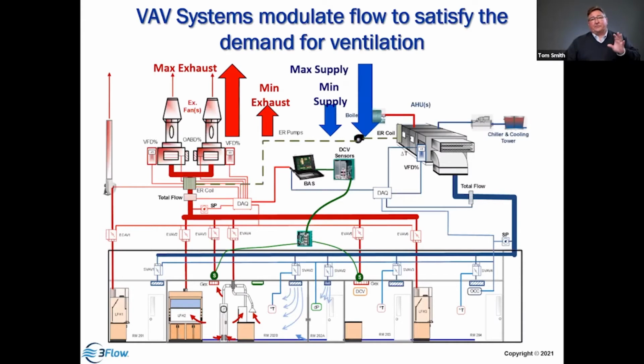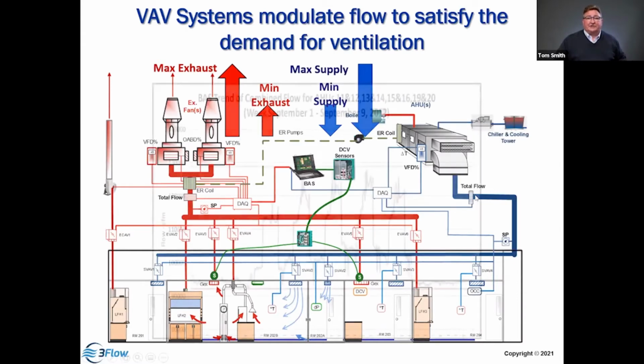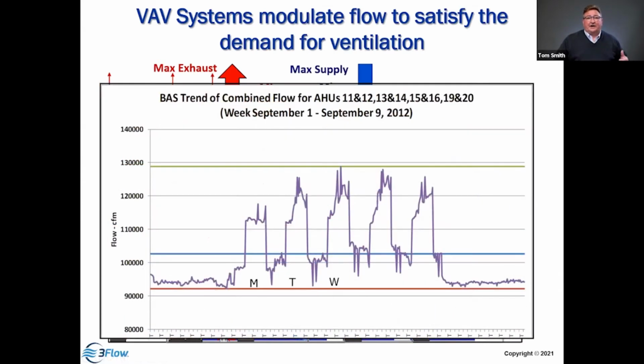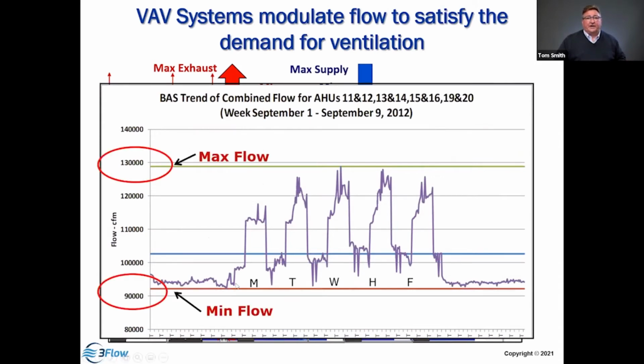So we're anticipating when we look at the system, we're going to see modulation in flow. Well, if we were to trend the airflow, would we see that modulation? If we looked at the operation over, say, the course of a week, we start out on the weekends, it's at low flow, and over the course of the days, it starts to modulate. And as we get to the maximum, maybe that's a Wednesday in the middle of the day, we're at the maximum peak load, right? And then on the weekends, it goes back down to minimum flow. So now we have some understanding of this correlation between occupancy and operation.